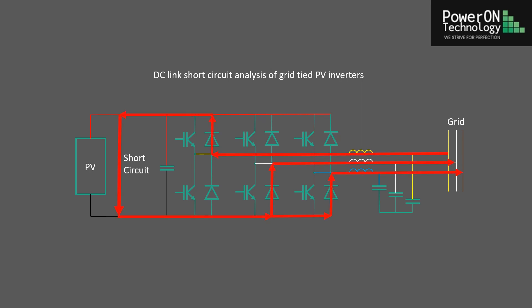The first fault current is through the freewheel diodes of the inverter. The inverter becomes a three-phase rectifier connected to the grid via the LC filter. The short circuit current flows from the grid through the filter inductors, freewheel diodes into the short circuit. The current is limited by the filter inductors, which makes the fault more severe because any series protection in line with the inductors, like fuses or circuit breakers, takes longer to trip because the fault current is most likely in the overload part of the trip curve.